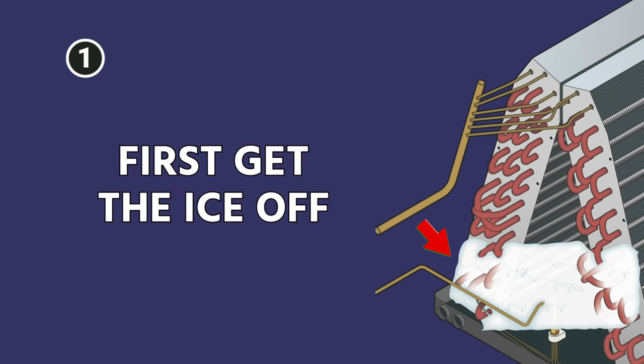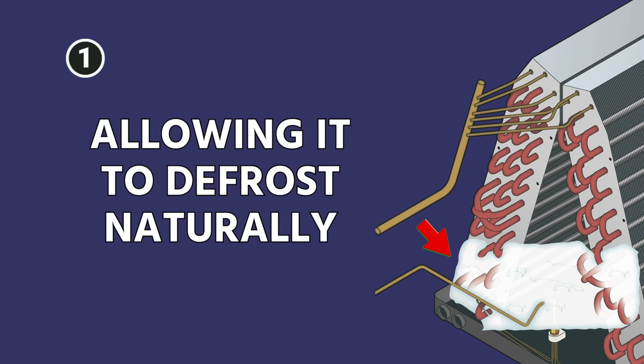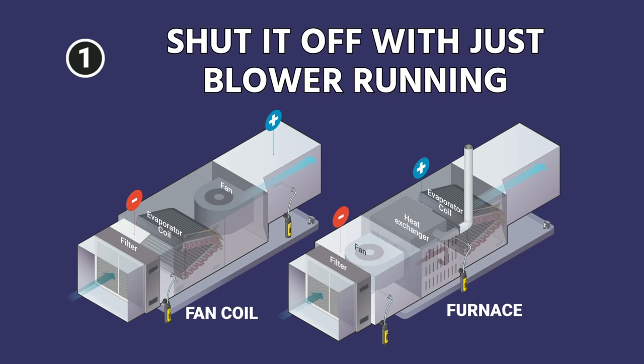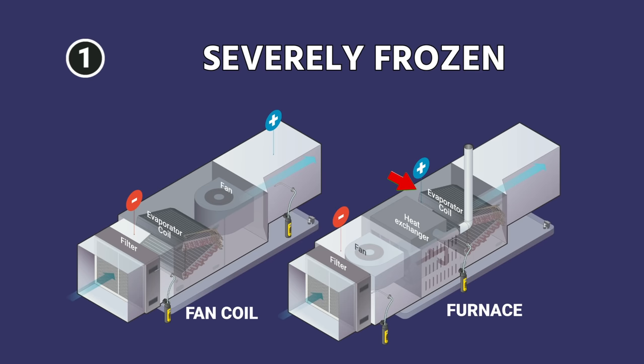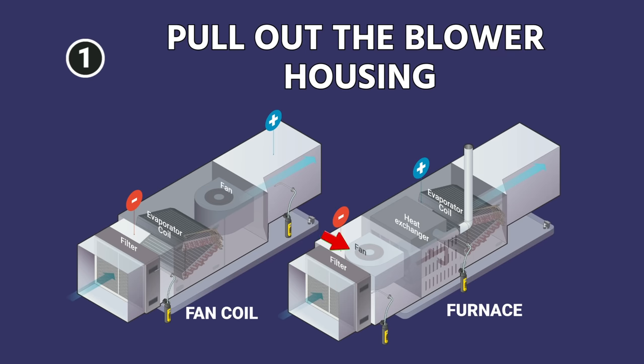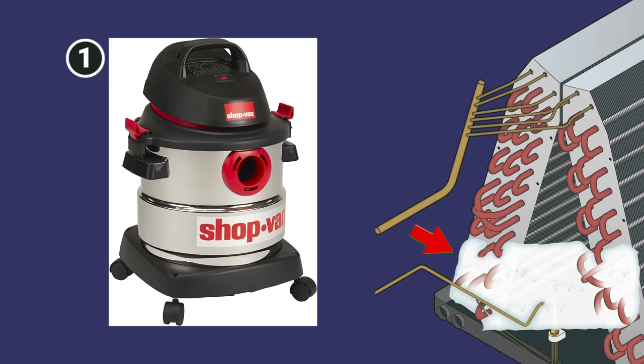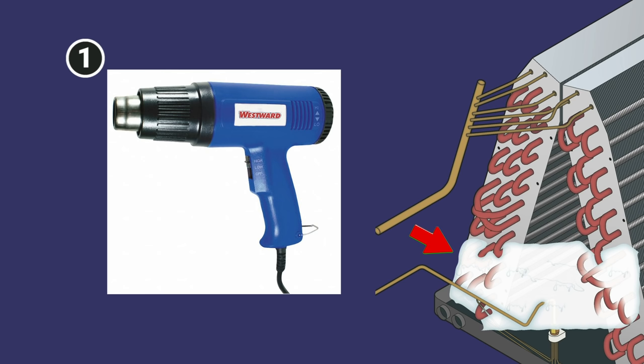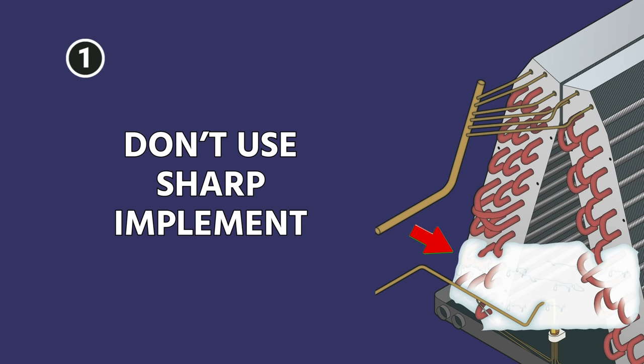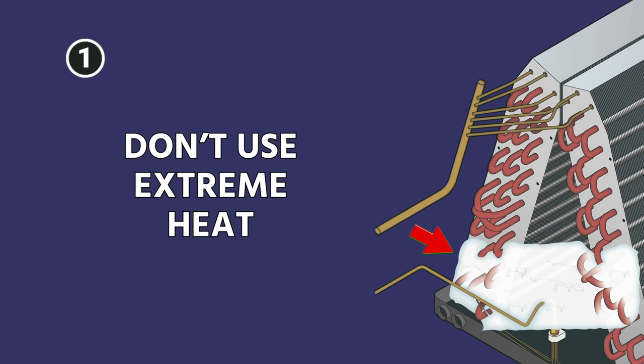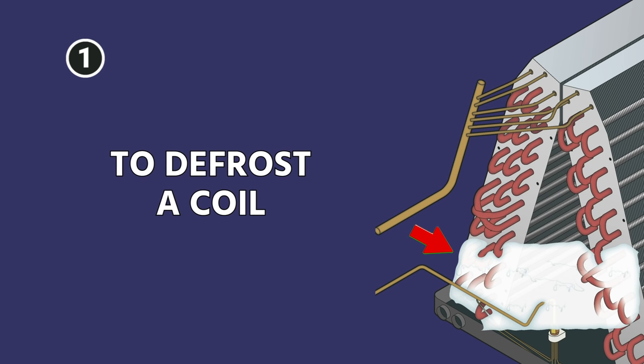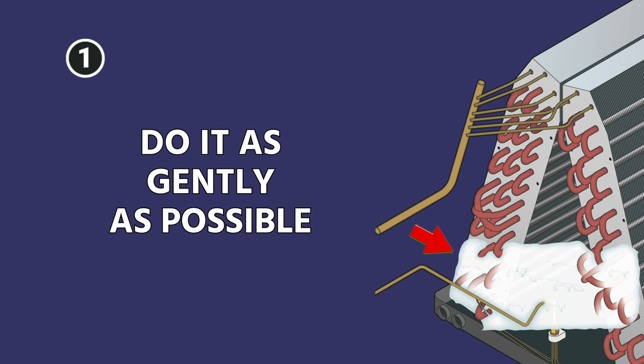First, get the ice off. In most cases, this is just going to mean allowing the thing to defrost naturally — shut it off with just the blower running in the case of a fan coil with the blower over the coil. If it is a gas furnace and you have a severely frozen evaporator coil, then you're going to want to pull out the blower housing and try to manage that ice as much as possible. As it melts, use a shop vac. In some cases you can use a heat gun or something of that nature. Don't use any sort of sharp implement or any extreme heat to try to defrost a coil.